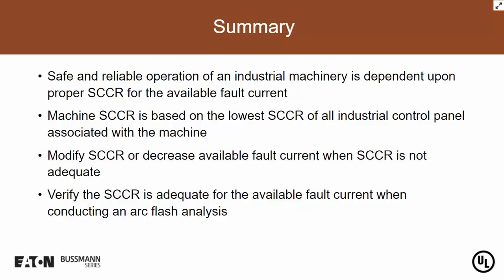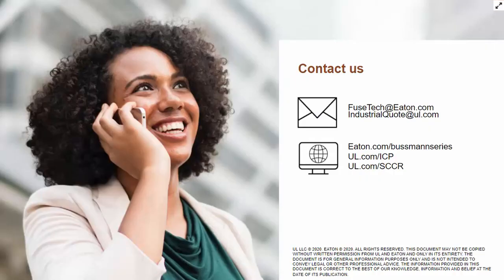I'll take that, John. When we're determining the SCCR for UL listed industrial machinery, we must use UL 508A Supplement SB and use that method to determine the SCCR. NFPA 79 is the standard or guide to build the industrial machinery itself, how to build it and what kind of requirements you need. But UL 508A SB gives us the guide to determine the short circuit current rating itself.